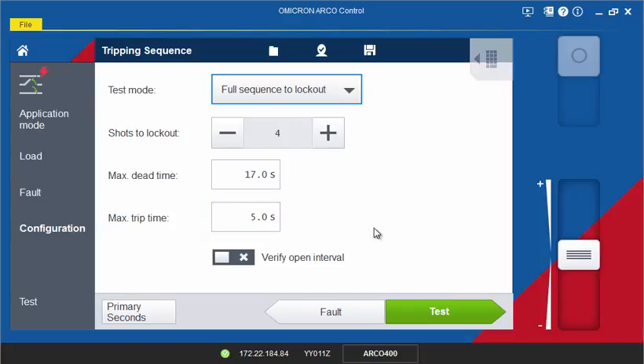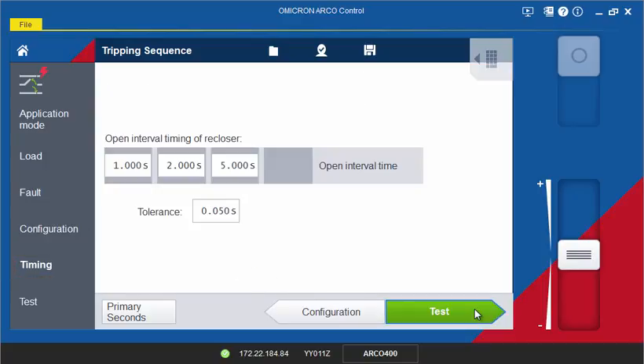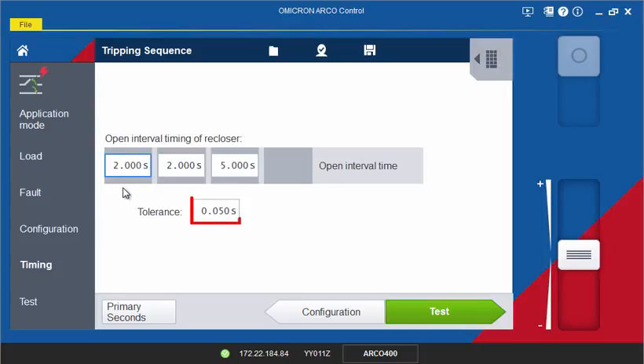If Verify Open Interval is enabled, the open intervals of the reclosing sequence can be assessed. Additionally, the timing page is added to your test procedure. Enter the duration of the open intervals parameterized in the recloser control and add a tolerance.